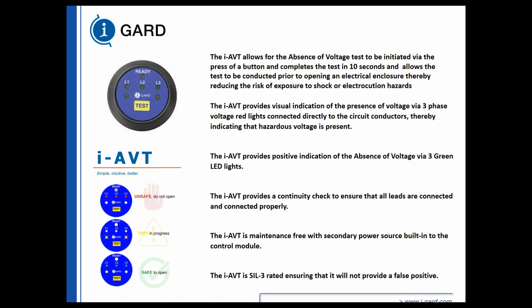So we only get 3 green LEDs once we verify that the phase to phase and phase to ground is less than 3 volts, AC and DC. We ensure that the continuity of the device is tested and operating properly as per manufacturer's recommendations, because we actually do that test twice on the device before the green LEDs come on.